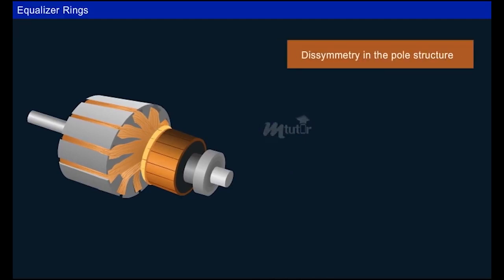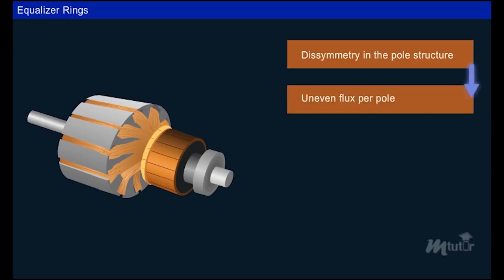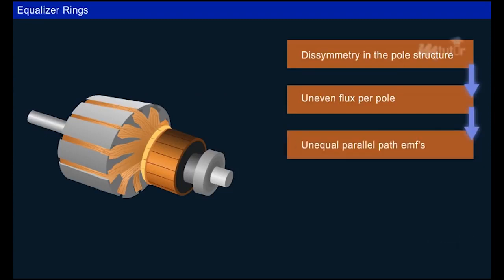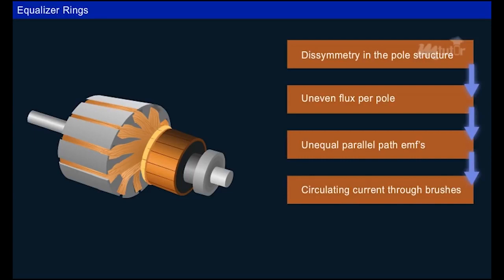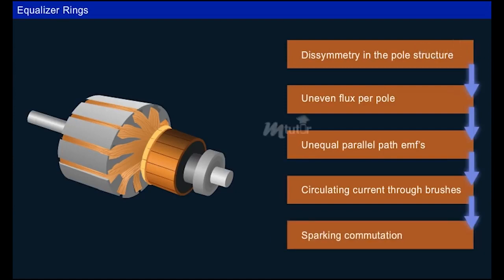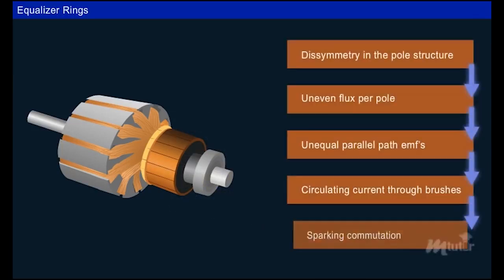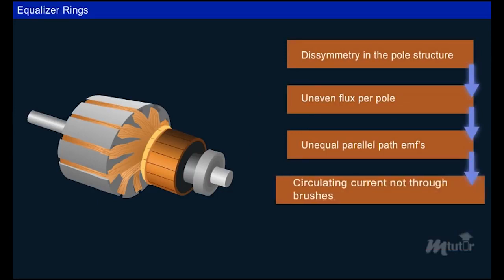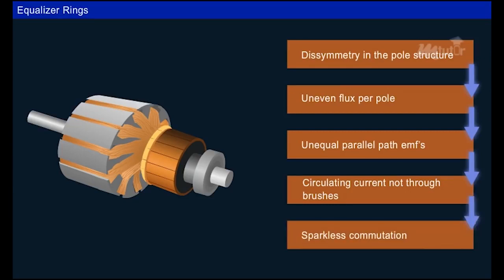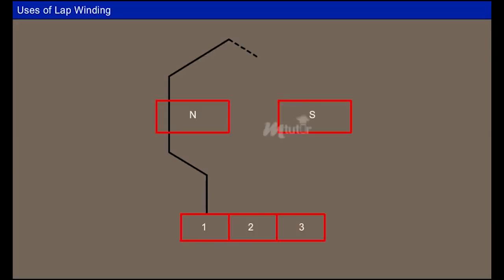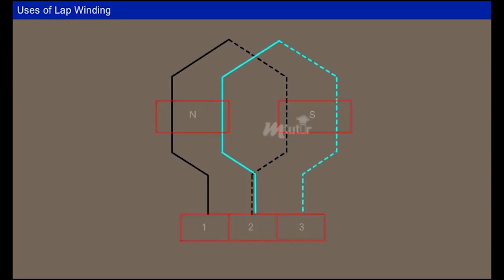These terminologies are essential to design armature windings in DC machines. Due to possible dissymmetry in the pole structure, there is uneven distribution of flux per pole and EMF in the parallel paths, causing unequal circulating currents through the brushes, leading to overheating and severe sparking during commutation. Hence, equalizer rings are used to avoid such overheating and sparking. Equalizer rings route the circulating current to the coil itself and help produce equal EMF in the parallel paths, resulting in sparkless commutation.